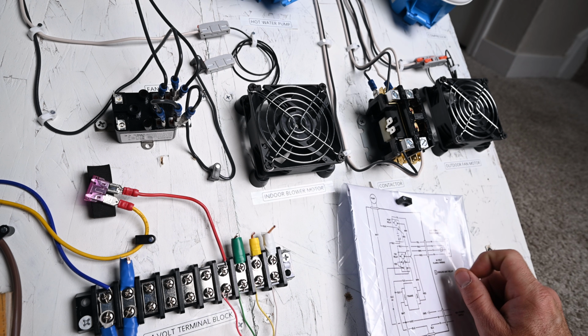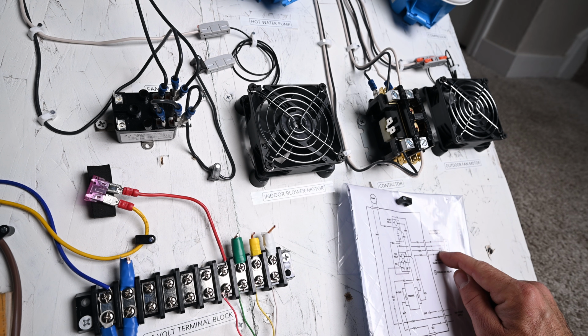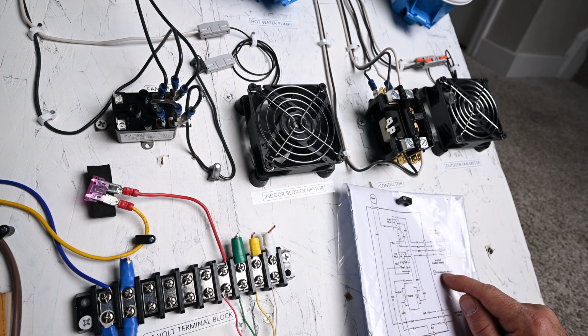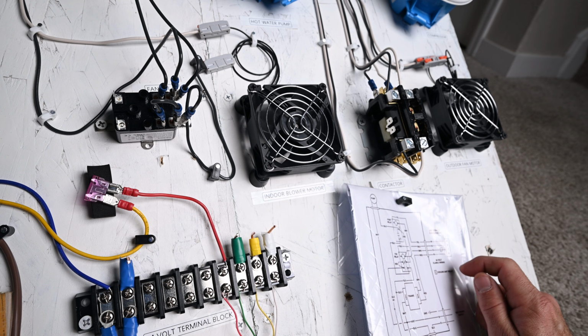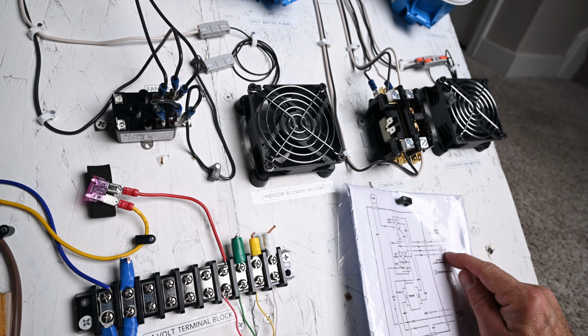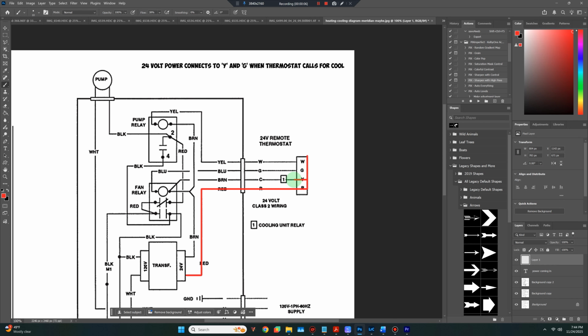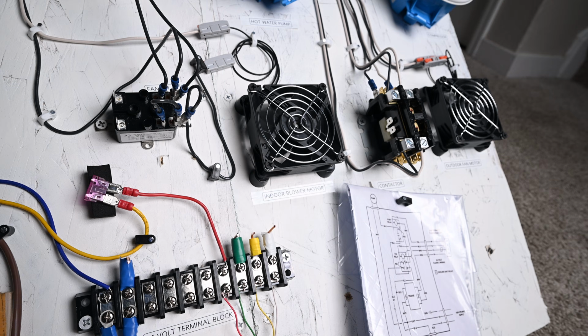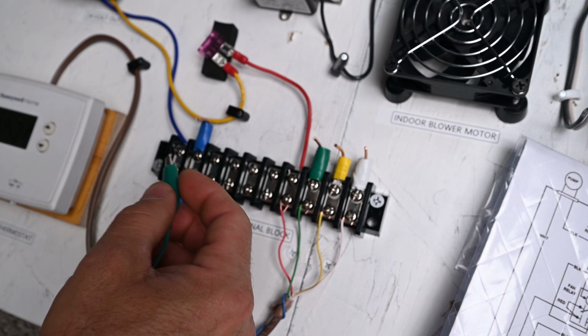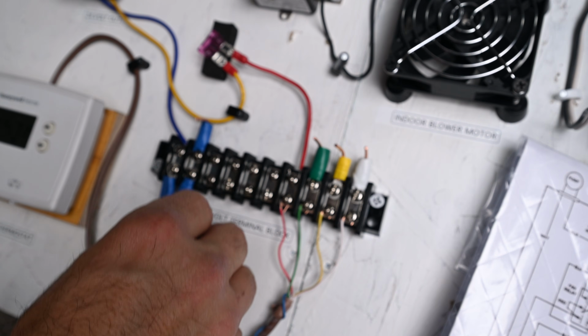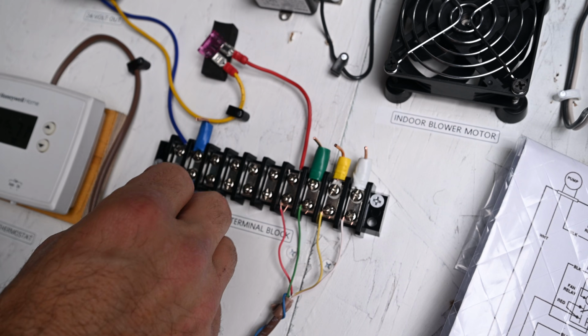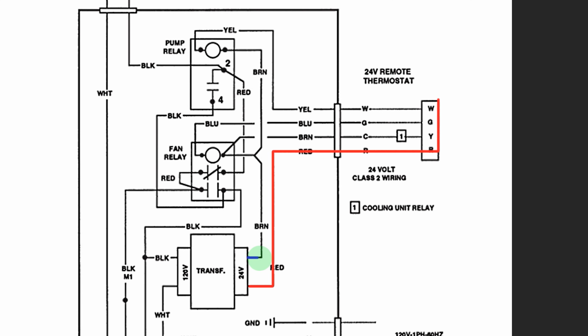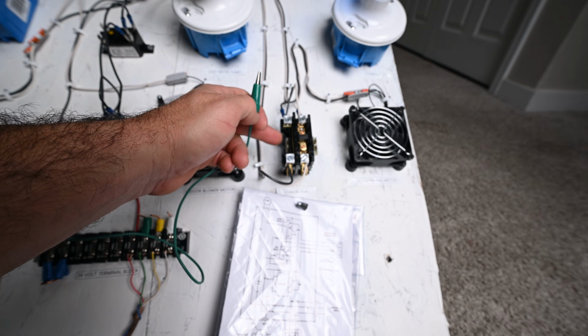So what we want to do is hook up the low voltage to, on this diagram, number 1, the cooling unit relay, also known as a contactor. To do that, we need one wire from Y to go to the coil, and we need one common to go to the coil. So let's hook that up. I used 4 of these lugs as the common terminal because to make everything on the board work, I'm going to need a lot of room on this common. So I'm going to hook one up to the common, and the other is going to go to the 24 volt coil on the contactor.